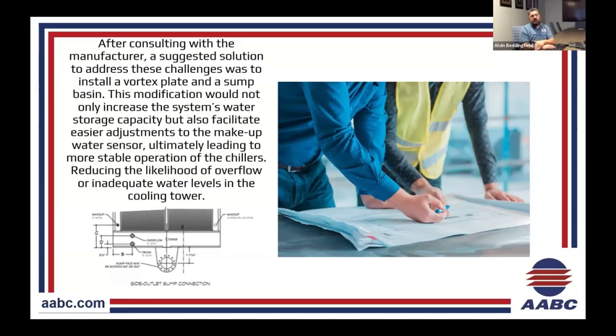Because as I said, it was going back and forth, like, okay, we've got this issue, here's the next issue. And terribly enough, I felt terrible for the mechanical contractor, because reconfiguring piping is not easy. So he's on an overnight crew. Issues established. All right, school's out. Cut the pipe, re-weld it, reconfigure it. Round 2, turn it off, cut the pipe, reconfigure it. Round 3. And it's not an easy task to keep having to break all your welds and recut and redo all your piping and order all the correct fittings every single time.